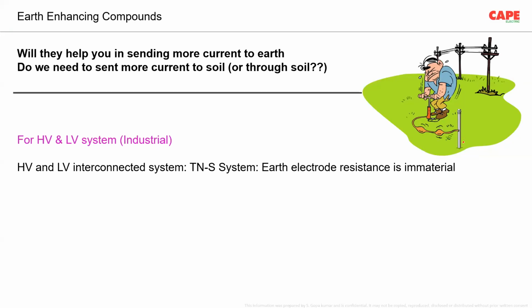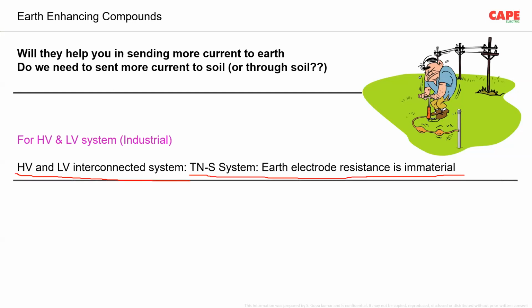In that particular case, if you go for an HV and LV interconnected system, that means the HT side and the LT side are interconnected, and your LT is a TN-S system, this is the recommendation of the standard. In that particular case, earth electrode resistance is immaterial, meaning you don't need to measure, or you don't need to have an earth electrode of 1 ohm or 5 ohm or 10 ohm or 20 ohm or whatever it is. That is immaterial.